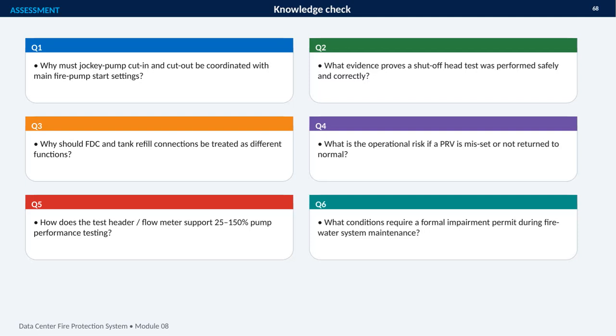This knowledge check brings together the main operational decisions from Module 08. As you work through it, focus not only on what each component does, but on how the components interact during testing and emergencies. For question 1, consider why jockey pump cut-in and cut-out pressures must be coordinated with the main fire pump start settings. The goal is to avoid unwanted starts while still maintaining system readiness. Question 2 asks what documentation and safety evidence demonstrate that a shutoff head test was completed correctly.